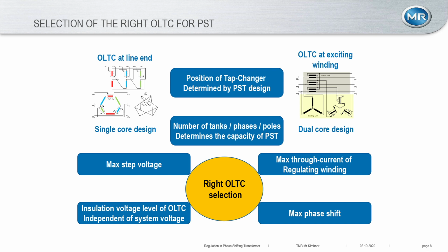And another critical thing is, as I already mentioned, you have to look at the short circuit and your needs there in the grid, because if you go to the K position with this design, you don't have any impedance in the grid anymore. So there's nothing that would limit a short circuit here. If you look at the design at the right-hand side, it's a two-core design. And the onload tap changer here is sitting in the star connection, and you have the possibility with the different ratios of booster and exciter to come up with ratios that would allow you the optimal selection of an onload tap changer. And all other things are printed here that are important, such as the step voltage and the max through current, of course. The phase shift has an impact as well on the step voltage. And insulation, of course, is critical for the OLTC here.